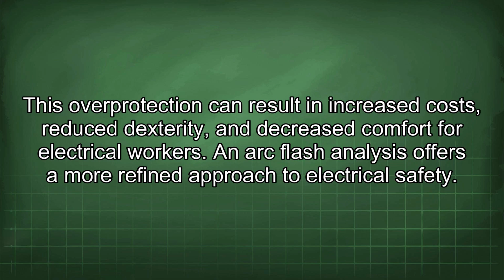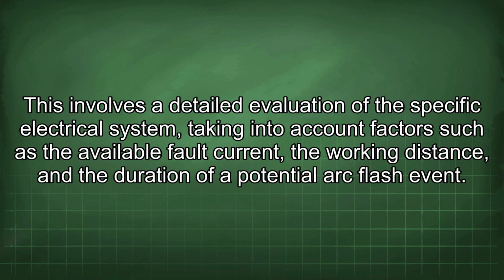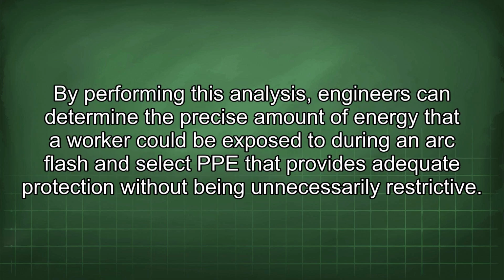An arc flash analysis offers a more refined approach to electrical safety. This involves a detailed evaluation of the specific electrical system, taking into account factors such as the available fault current, the working distance, and the duration of a potential arc flash event. By performing this analysis, engineers can determine the precise amount of energy that the worker could be exposed to during an arc flash and select PPE that provides adequate protection without being unnecessarily restrictive.